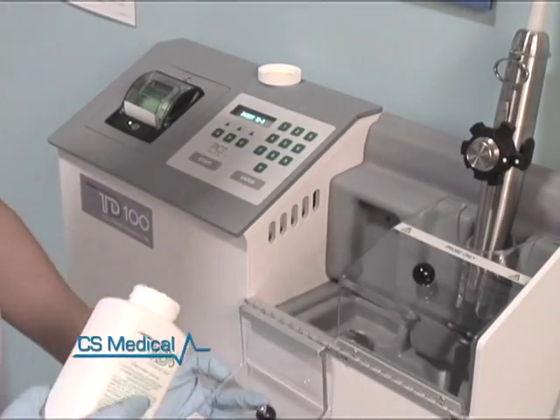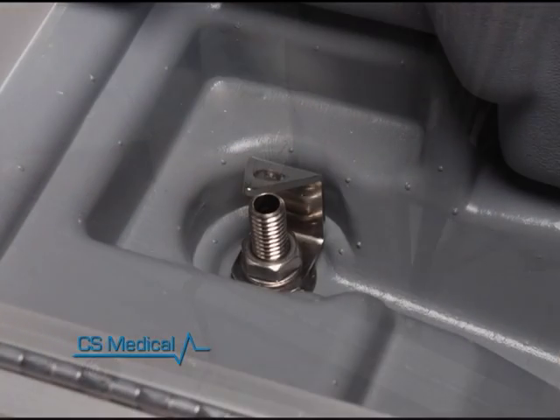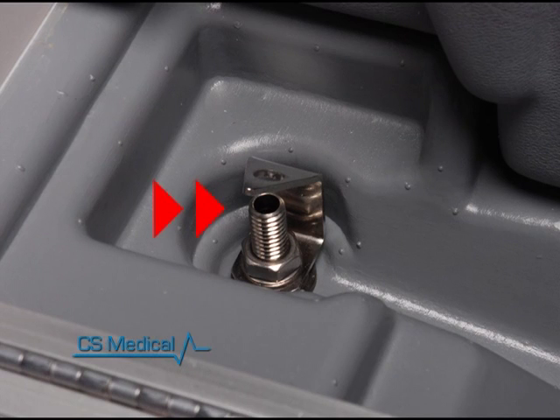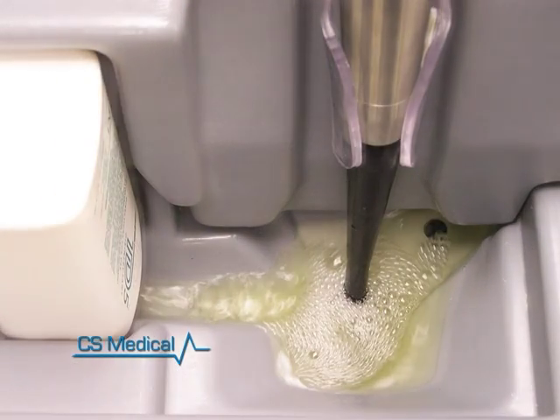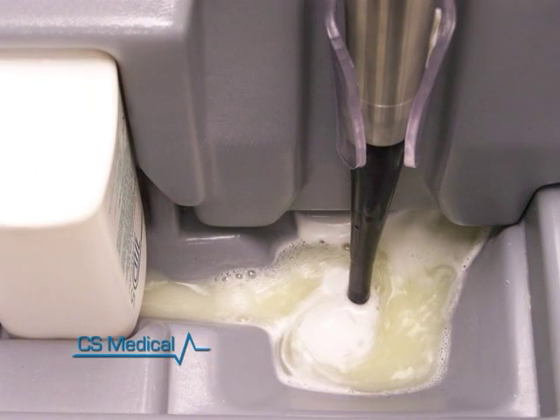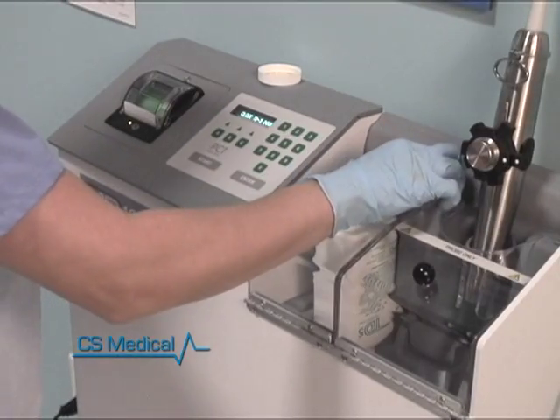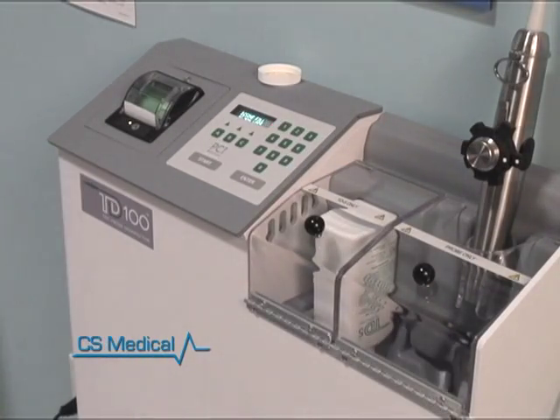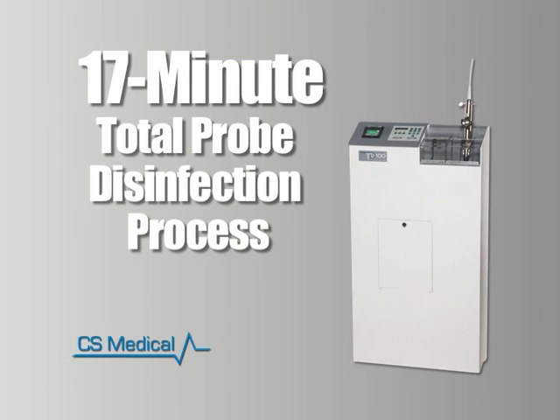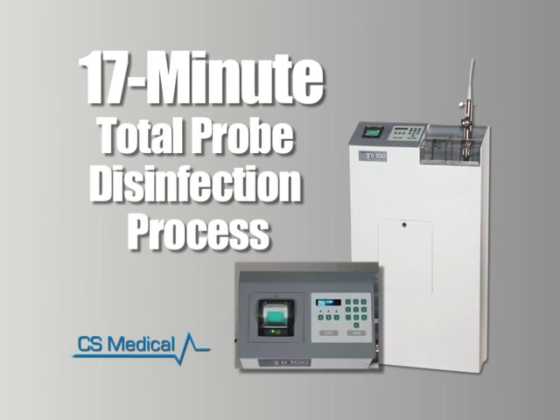Open the door labeled TD5 Only and tip the TD5 bottle into the reservoir. You will feel resistance as the piercer in the reservoir penetrates the foil seal. Disinfectant will begin to flow into the tube reservoir. Close the hinge door labeled TD5 Only, and the TD100 will automatically start the process of disinfecting the TEE probe. The total process will take 17 minutes. A countdown timer and cycle indicator is visible on the LCD during the disinfection cycle.